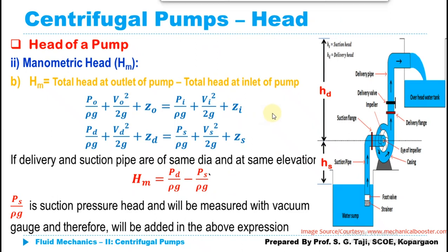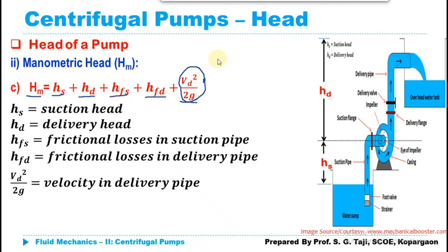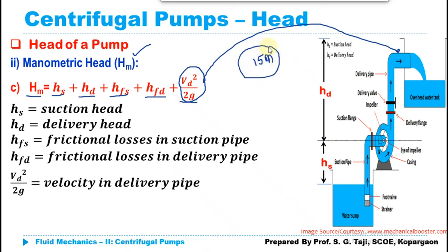Another expression for manometric head — by adding all heads — gives HM equals hs plus hD plus hFS plus hFD plus VD squared upon 2G, where VD squared upon 2G is the excess head available in the delivery pipe. These are the three expressions used to compute manometric head. Remember that manometric head is very important as it is used in computing efficiency — it is the head against which the pump is working. So when it is stated that a pump is working against a head of 15 meters, that value refers to the manometric head.